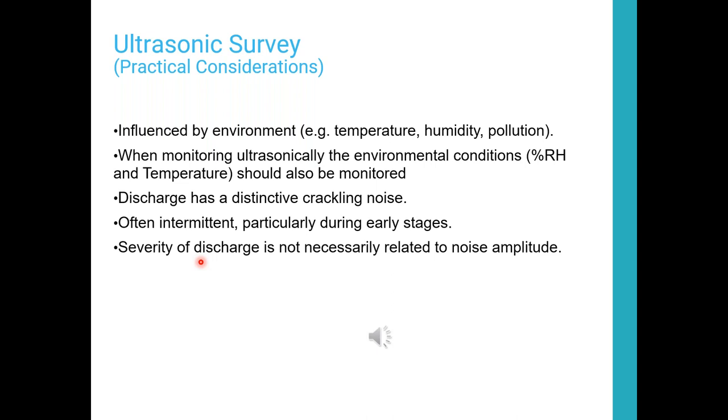And what we looked at was we had humidity monitors going also. And we saw that every time the humidity went above 60% in that room, the ultrasonic readings went from 3 dB to over 30. So significant increase in activity. Anything over 20 is considered serious with ultrasonic testing. And every time the humidity dropped below 60%, the partial discharge activity dropped down to essentially none.